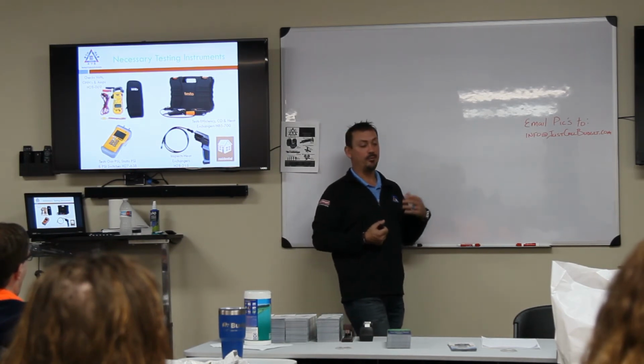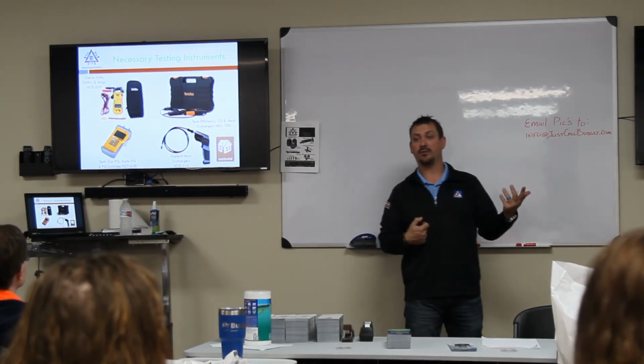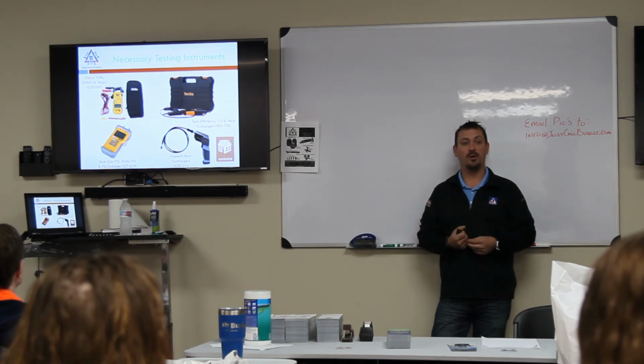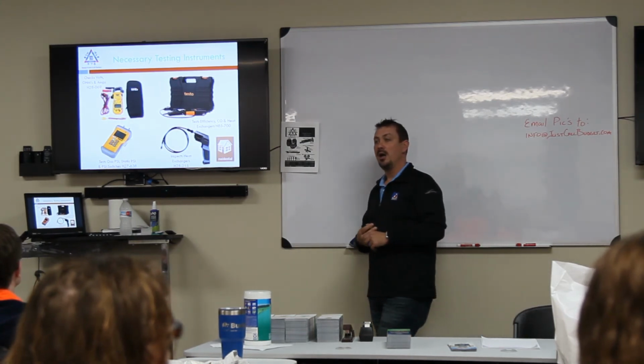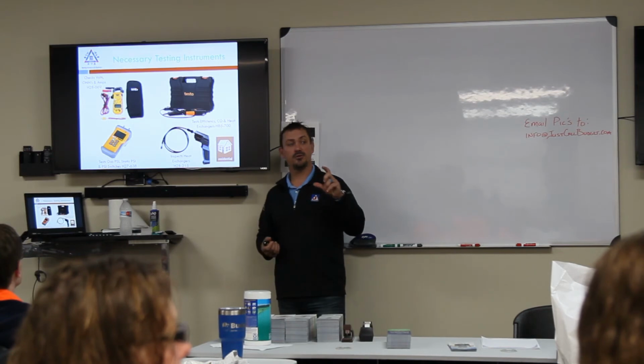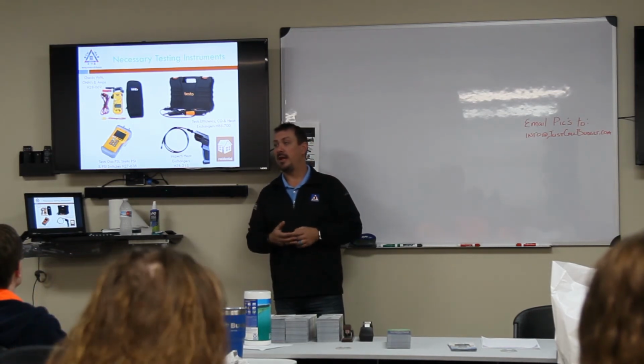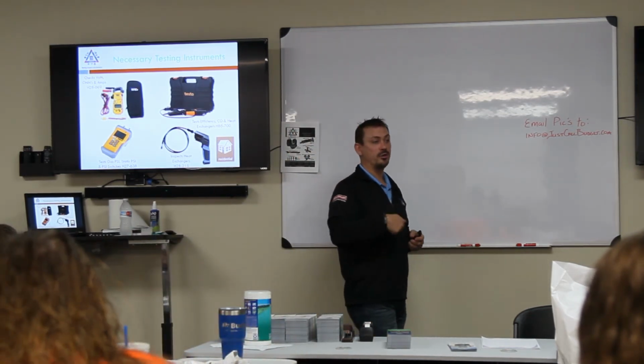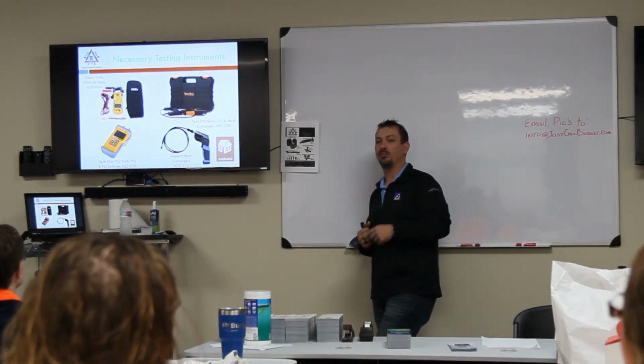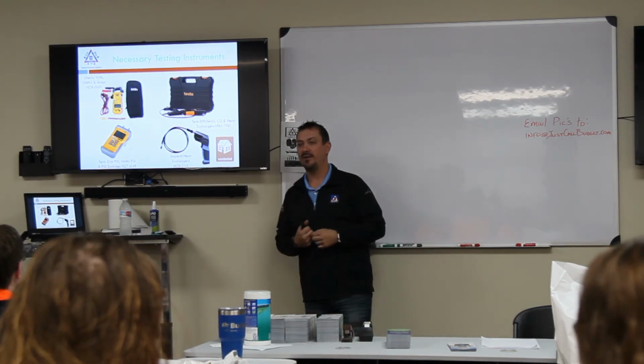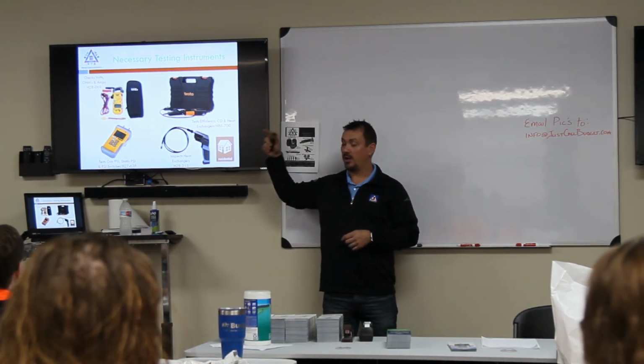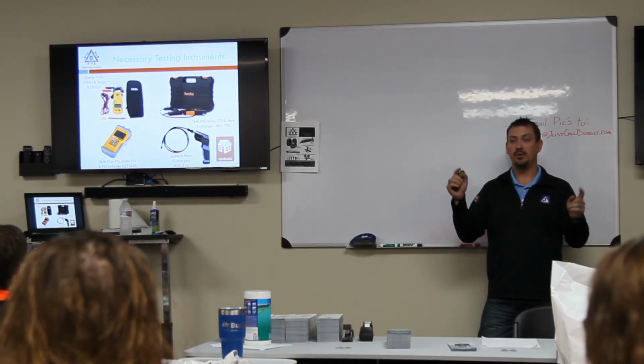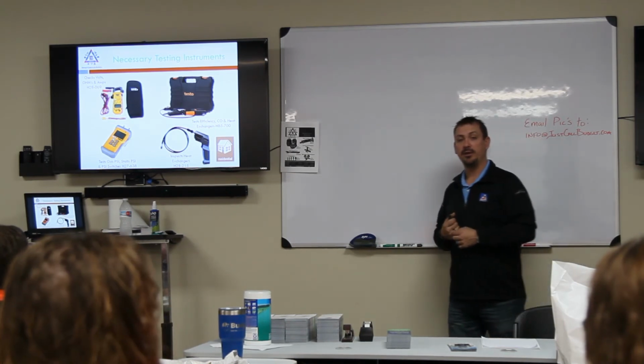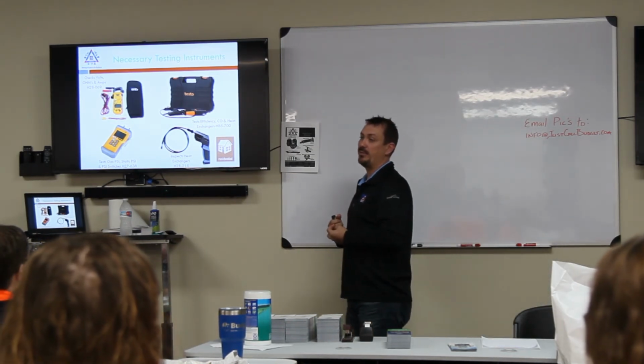So if you have a pressure switch that has failed on you or that's currently not reading properly because it's wet, and you don't want to wait two and a half days for it to dry out, then you can take a universal pressure switch, which I'm a big fan of, turn the pump on and turn it up to 0.65 if that's what the pressure switch was at. Then you can dial that universal pressure switch to exactly 0.65, and there are leads on that Fieldpiece meter that will show you that the switch is closed, and then you know that you dialed that in exactly to the specs of the manufacturer.